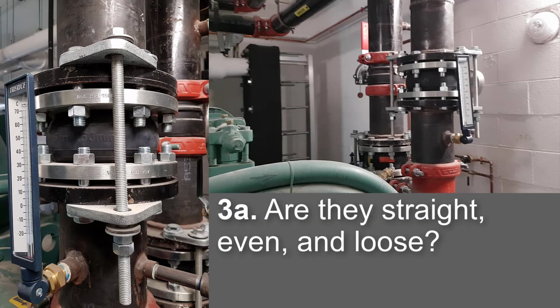They do appear straight and aligned with the center line of the pipe. The two rods are evenly distributed around the pipe, being on opposite sides from each other, and they are loose on one of the two pipes but tight on the other, as we saw in the video. So this one is a maybe. It would be good to try to loosen up the control rods, but if there aren't any noise problems, it could be left as is.